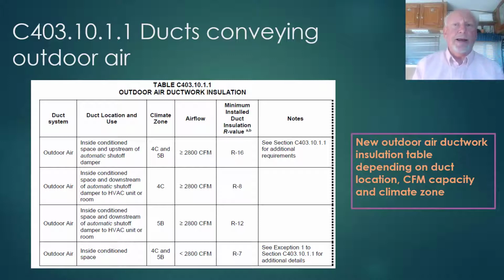If it's ductwork that's serving outside air to a DOAS system, an ERV, or an air handling system, we now have specific insulation requirements depending on where the ductwork is located and whether it's upstream or downstream from an isolation device, based on the airflow, based on the climate zone, and then a defined minimum insulation value. So, for example, if you've got outside air ductwork that's serving an air handler, the minimum outside air is greater than 2,800 CFM, and it's located in climate zone 4C, it's required to be insulated to R16. So hopefully this will clarify the insulation requirements for outdoor air ductwork connected to air handling systems, including DOAS systems.